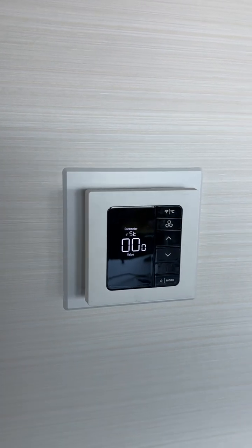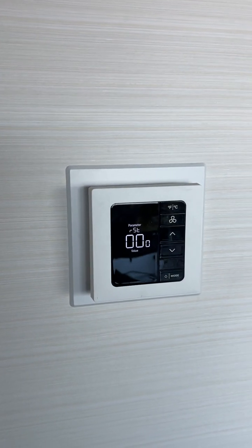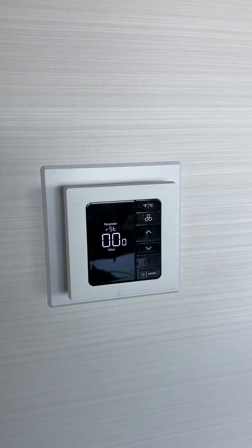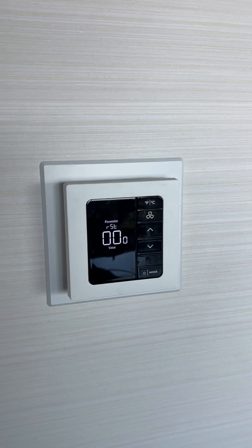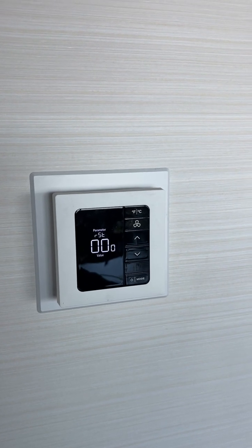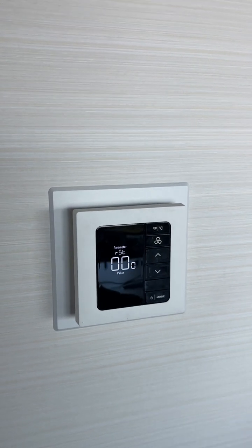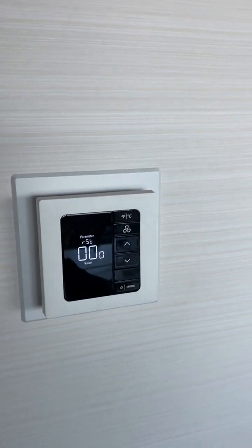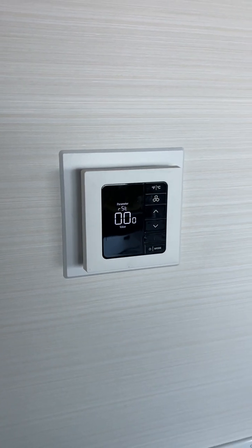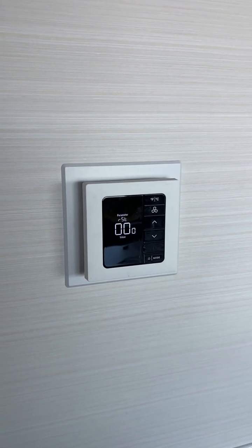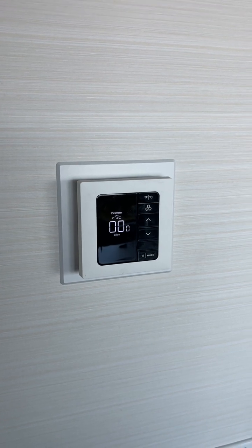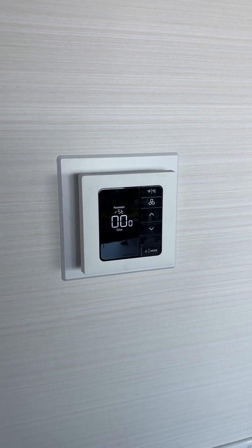You could just power cycle it, turn the power off, or toggle the power to the unit. I prefer toggling the power because that will kill the thermostat temporarily. Then turning it back on, it boots up fully, and it's more likely to resolve a software issue than just a basic restart would. But a basic restart is still a good basic troubleshooting step.